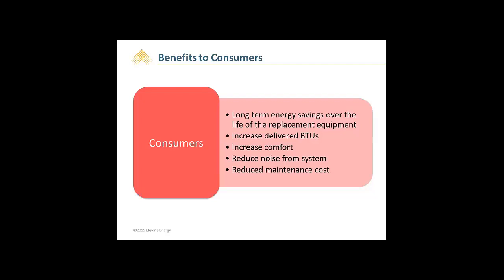SAVE can also eliminate the sound of restricted airflow caused by high static pressure. By having the static pressure at the manufacturer's specifications, you reduce wear and tear on the blower motor. This is really a win-win situation.